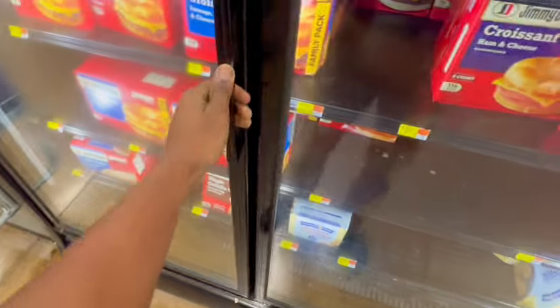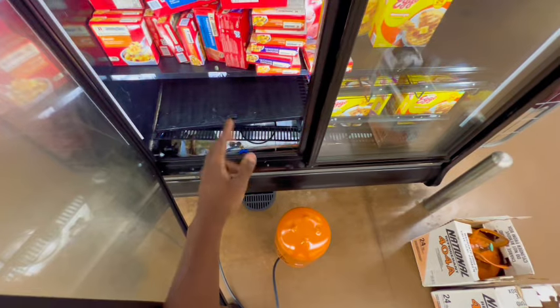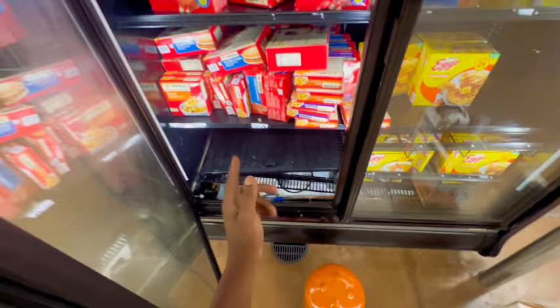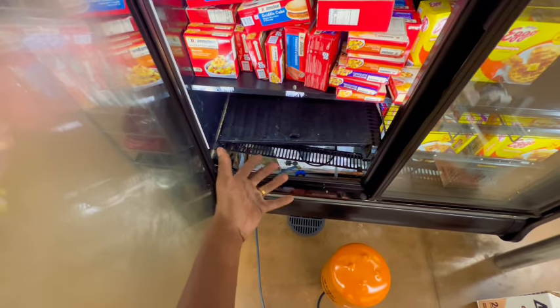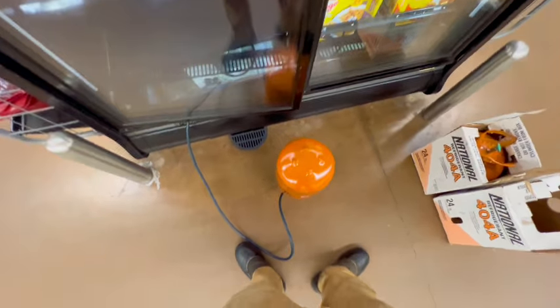Just finished that drum. These kicked on. All right, guys, we got 50 pounds in the system already. As soon as I put that in, the fans kicked right on. Now we got this pinch valve feeding liquid, but you can still hear it hissing and all that. It shouldn't be no noise. It should be quiet as a mouse. Typically, you're possibly starving for gas if you hear something like that.